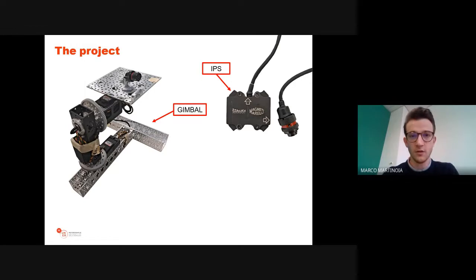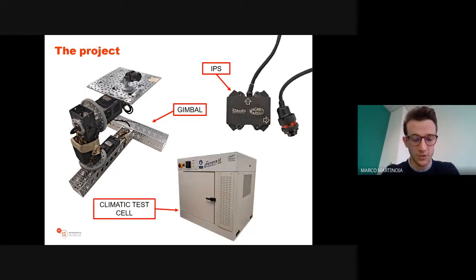To account for thermal deviation that can occur because the IPS is mounted very near to the internal combustion engine of the motorbike, the whole process takes place in a climatic test cell, which takes the whole system from 0 to 80 degrees while the calibration is performed.